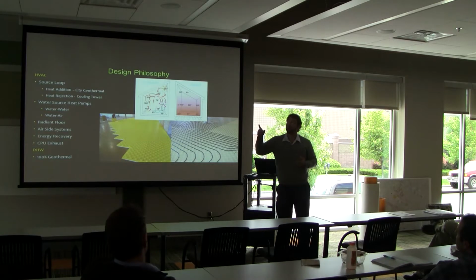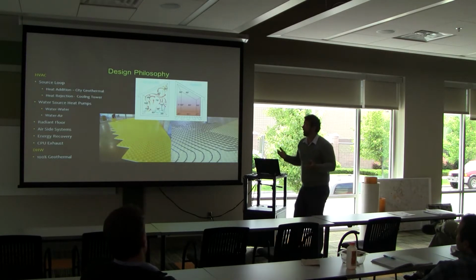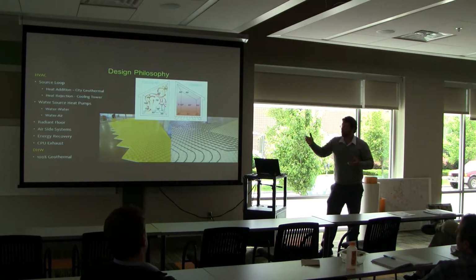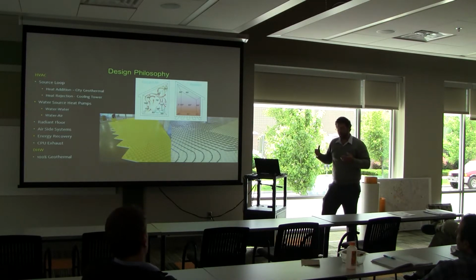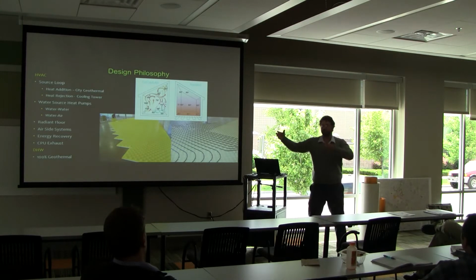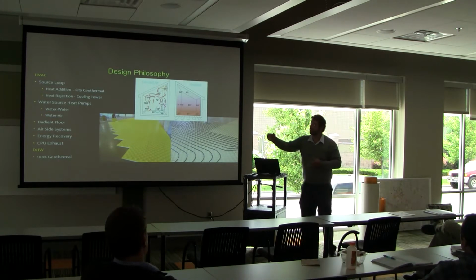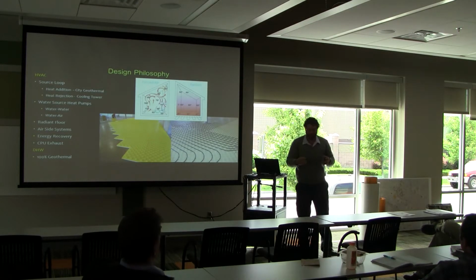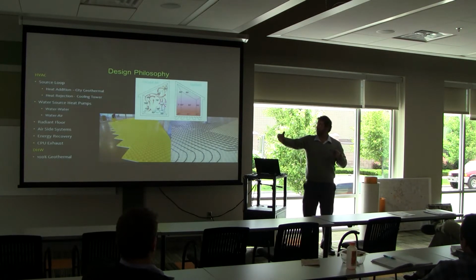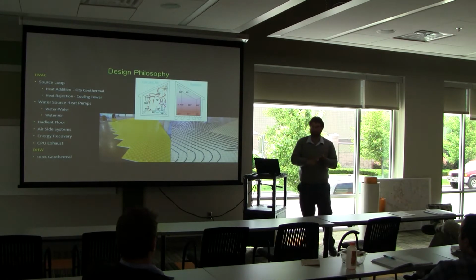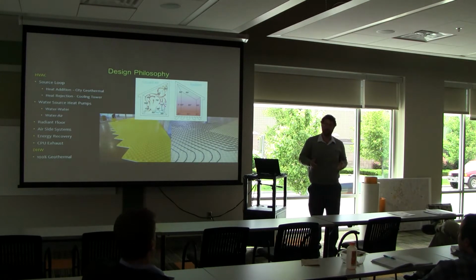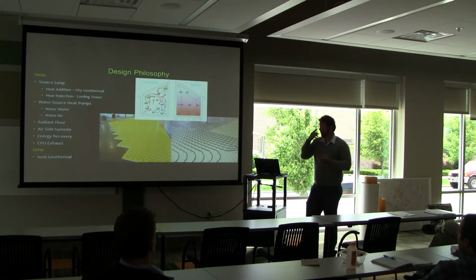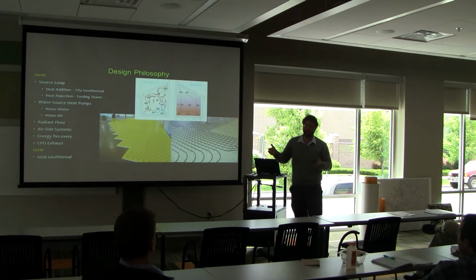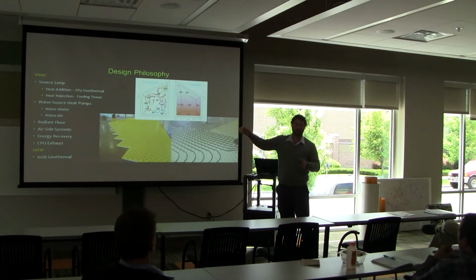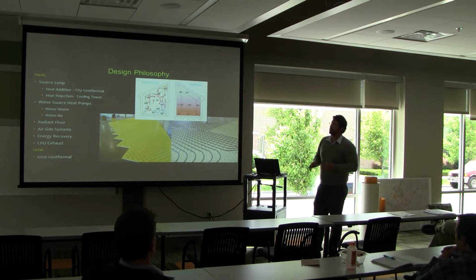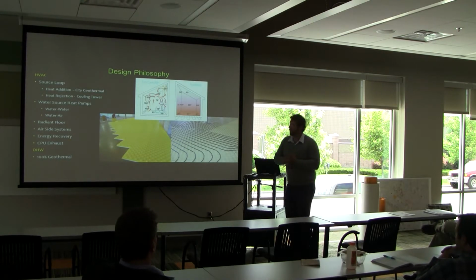We also use water to air heat pumps, which this system in here is a water to air heat pump. The idea behind a water source heat pump is that we don't stick our condenser up on the roof or outside and subject our refrigeration cycle to outside air conditions. By having this source loop available, the heat pump is allowed to operate consistently throughout the year at its peak efficiency and capacity. So if it's 0 degrees out, your air to air heat pump, which is the traditional heat pump, actually loses capacity exponentially after 30 degrees. We don't lose any capacity this way. So the HVAC system is not relying on the outdoor air whatsoever.